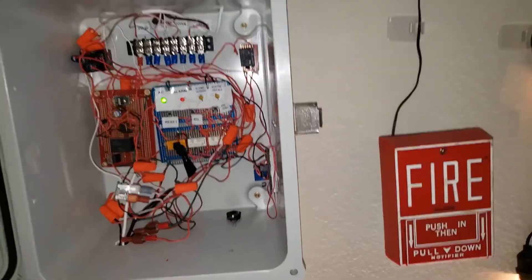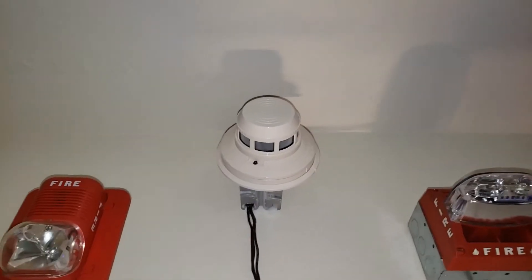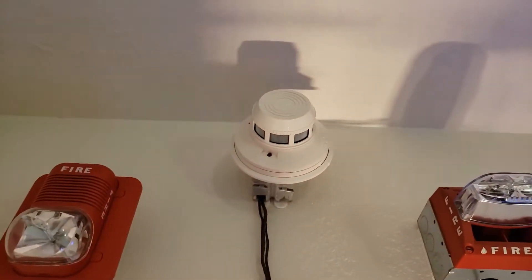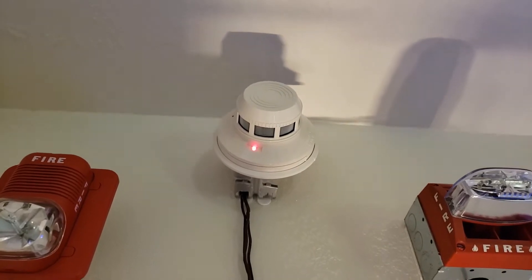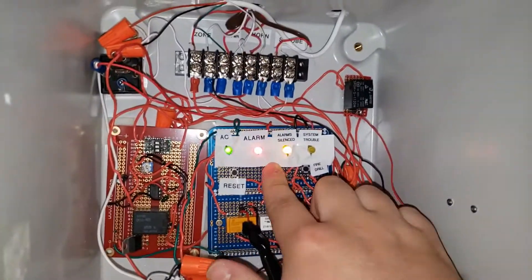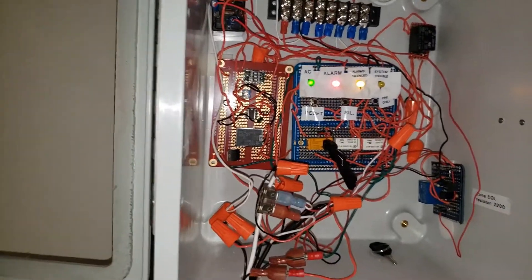Here's the panel. So now we're going to do the 2424, and I'm going to be using the Smoke Sabre and test it with that. Here we go. It's doing 120 beats per minute, as you heard.